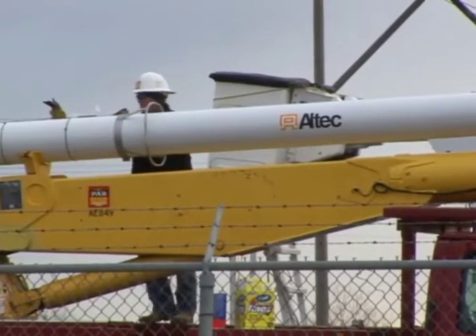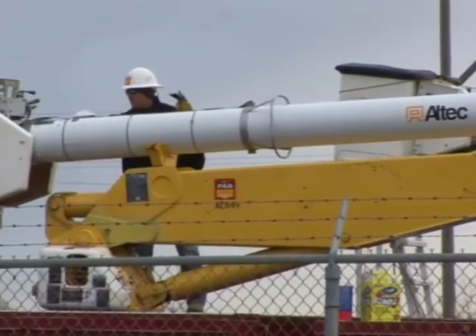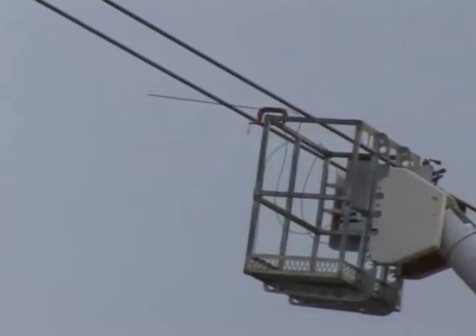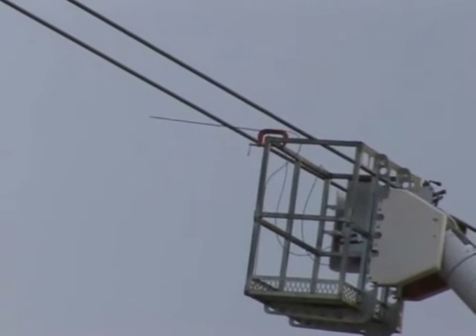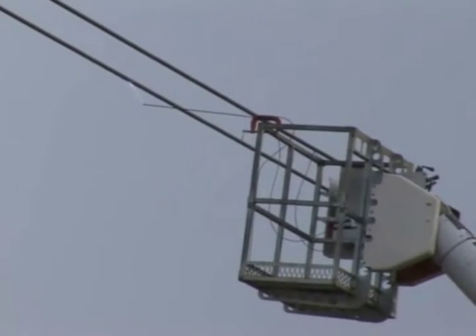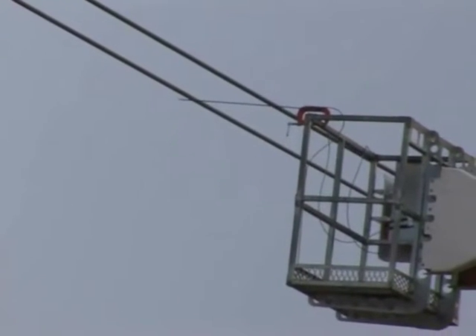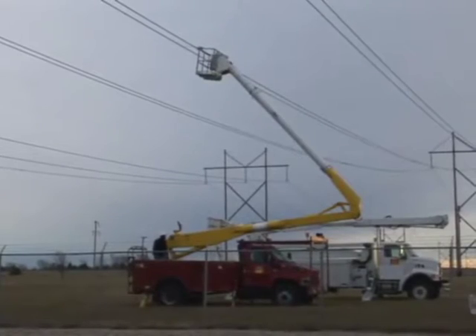Before any work can begin, PAR must perform a voltage test on the bucket of their truck. The bucket is energized to the appropriate voltage. In this case, PAR used the Rose Hill line just outside the substation for its testing. Testing must be done at the start of the day in which the work is scheduled.